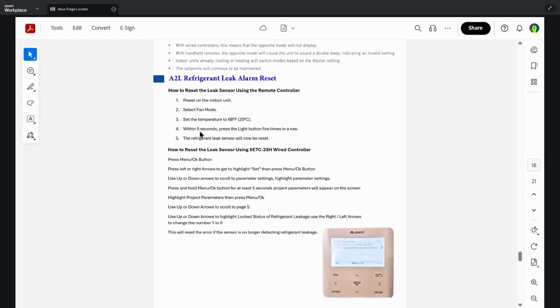Moving along, the A2L refrigerant leak alarm reset. Below is the illustration on how to reset the A2L alarm if it ever trips. So what you're going to do is power on the indoor unit, select fan mode, set the temperature to 68 degrees Fahrenheit, and within 5 seconds of doing that, press the light button 5 times in a row. And we know that this will actually reset the refrigerant leak sensor.